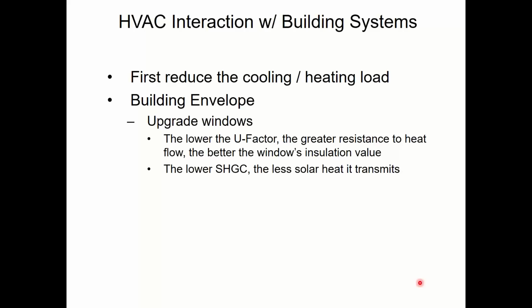but the windows, it's a little more important than the wall insulation in a commercial building because in a lot of commercial buildings, we have a lot of glass. Now, if you're in older buildings, you probably don't have a lot of glass. If your office building that you normally work at was built before World War II, it's probably really thick walls with a lot of masonry and small windows. And everybody has a perimeter window. It's probably in an H or an L or a C shape in order to get everybody a perimeter with a window. But the windows are probably relatively small to the building because we want the thermal mass of the building to keep the building cool because we didn't have any cooling, right?